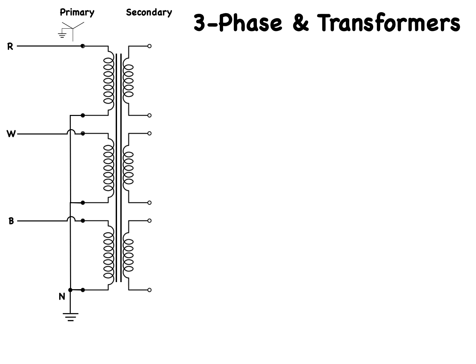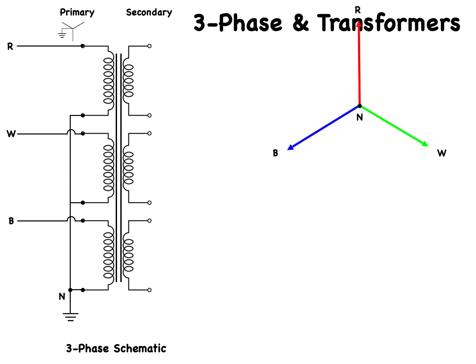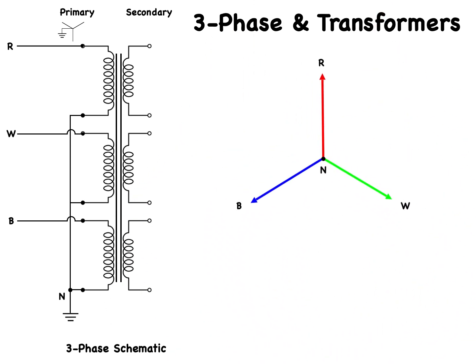What you see here is exactly what you would find on a three-phase schematic drawing, although the secondary connections haven't been shown yet. A very important point: we are dealing with AC voltages on the primary. Even though we are connected to a three-phase source, each transformer will only see one AC voltage and will handle it as such — either stepping that voltage up or down, in phase with that one voltage. Because it is a balanced system, the voltages are equal in magnitude and 120 degrees apart, indicated with the colored vectors or phasors. Because we have connected the bottoms of the primary windings together, the phasor tails form a neutral, meaning we can move the phasors anywhere on our two-dimensional slide, but their tails are pinned — if you move one phase, all the rest have to move likewise.